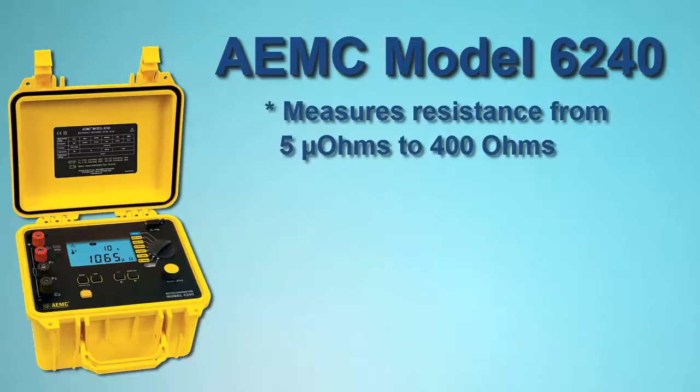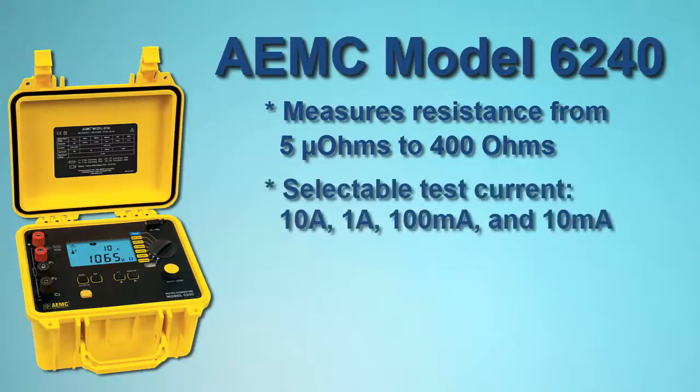The Model 6240 measures the resistance from 5 microohms to 400 ohms. The instrument provides selectable test currents of 10 amps, 1 amp, 100 milliamps and 10 milliamps and includes a polarity reversal function.